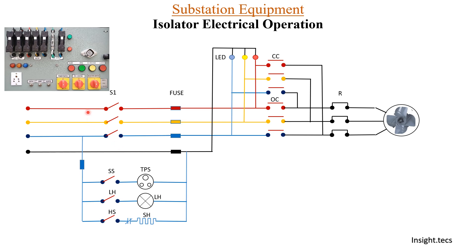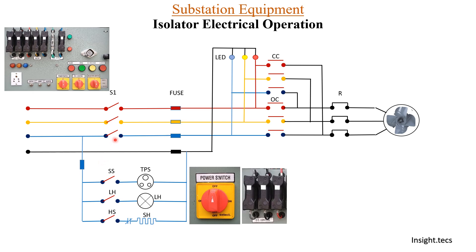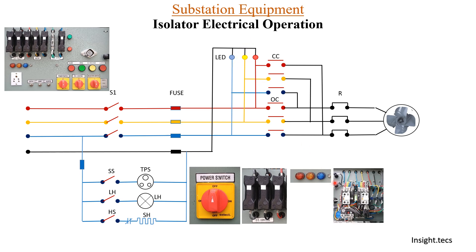The power circuit has three phases and a neutral — R, Y, B phase. S1 is the switch connecting the power supply. After the DC control fuse there is an LED that glows. After this, the contactors come into picture: CC is for closed contactor and OC is for open contactor. After this, the power supply reaches the motor through an overload relay.